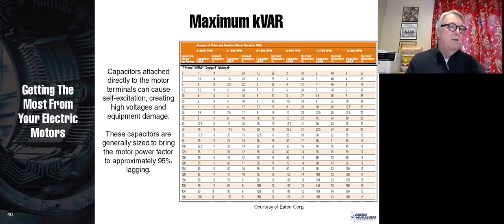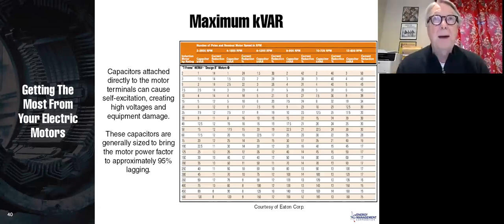Now, maximum kVAR. If you have a capacitor on a motor system and that capacitor gets too big, then that can self-excite the motor, and the motor can reach very, very high voltages. The problem here generally is when you put capacitors in the conduit box of the motor, and then you turn off the circuit breaker. Since the capacitor's on the motor and the motor's still turning, they reach very high voltages and can damage the motor as well as the capacitor.